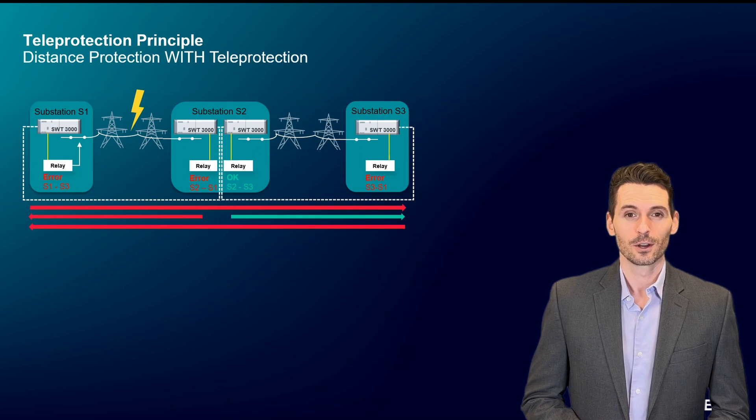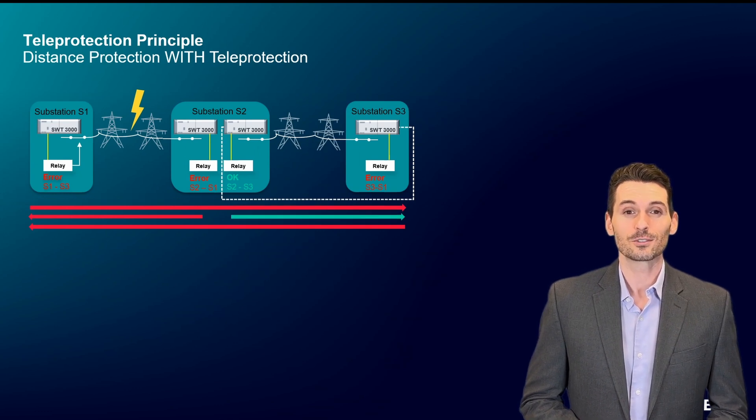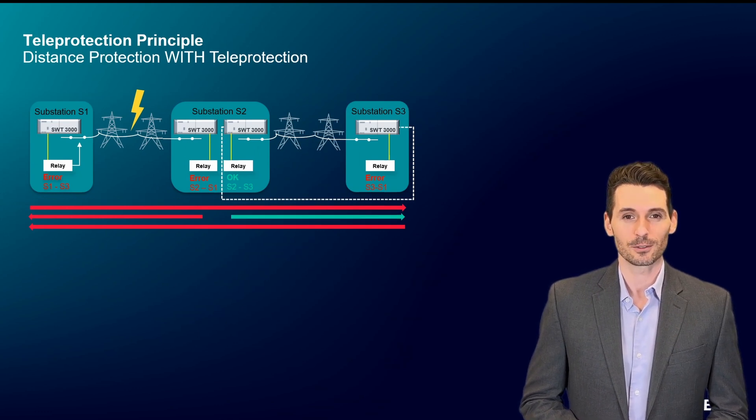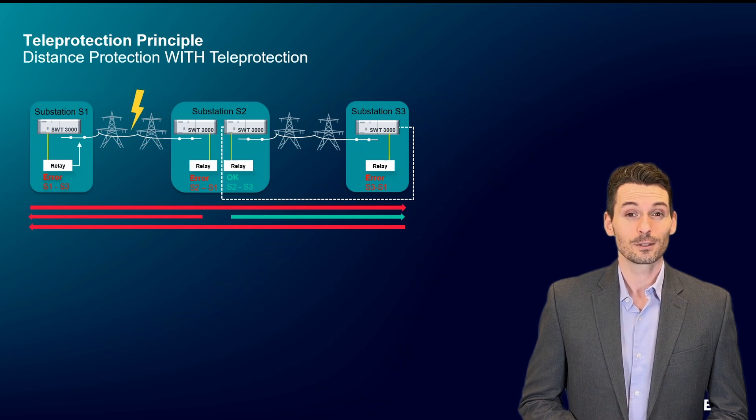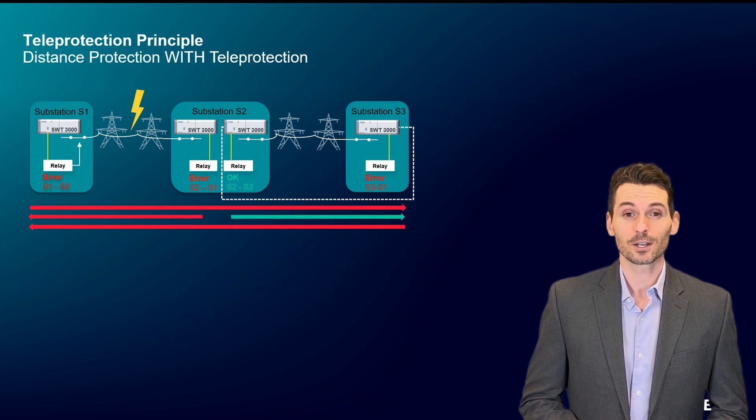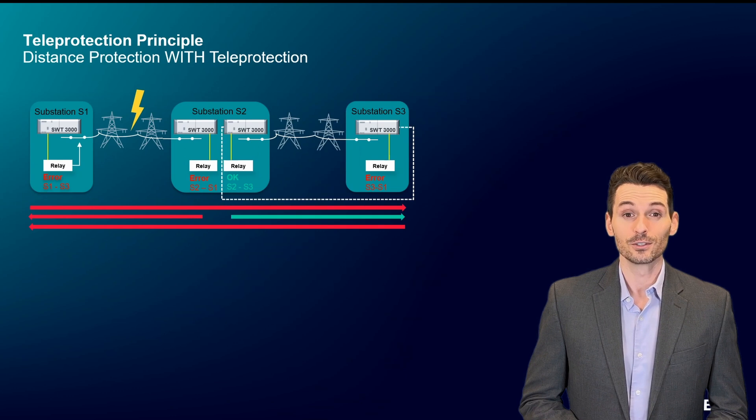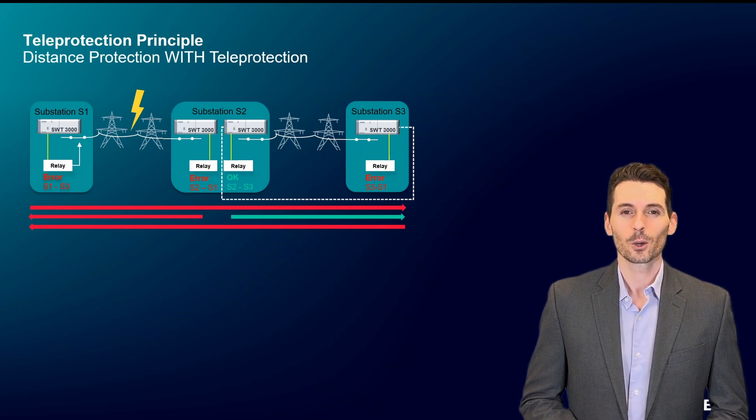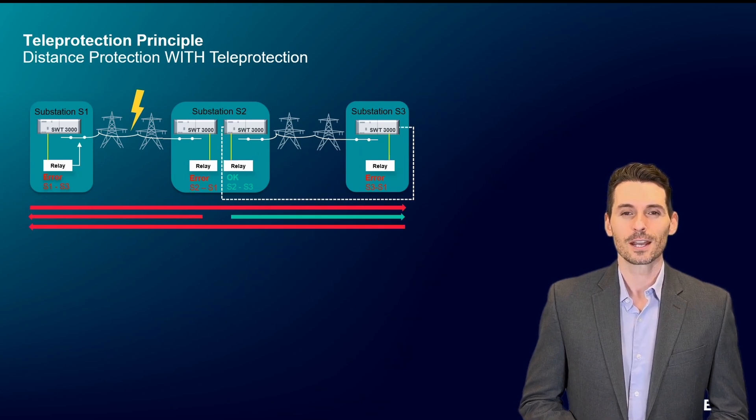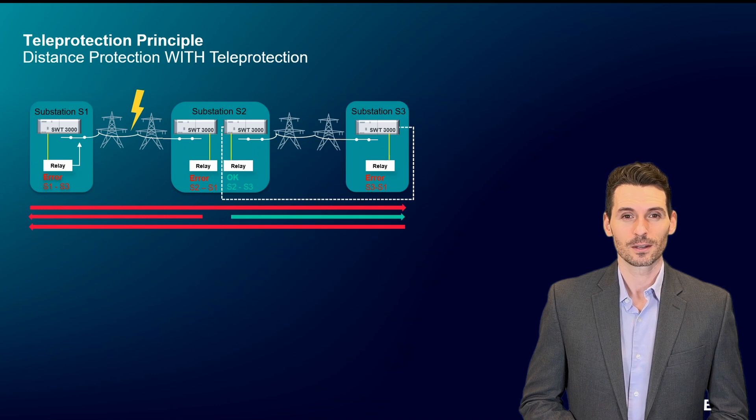Let's first look at the line between substations 2 and 3. Only the relay from substation 3 detects and reports an error to the assigned protection signaling equipment. The relay in substation 2 doesn't detect any fault.